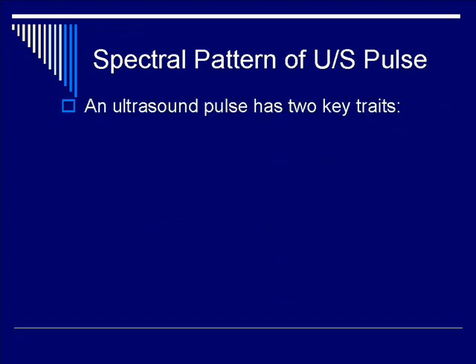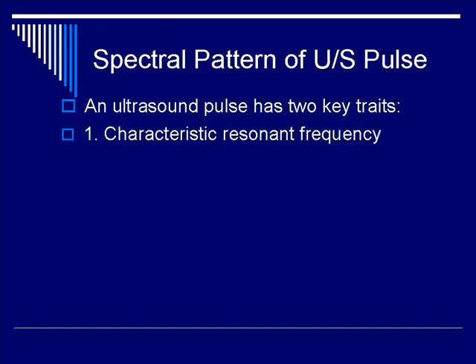The spectral pattern of an ultrasound pulse has two key characteristics. The first one is its resonant frequency, which is a characteristic of its piezoelectric element and configuration. The second element is the frequency bandwidth, which is a consequence of the pulse duration.